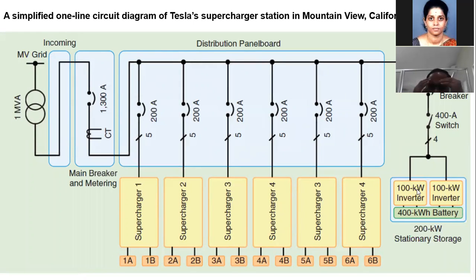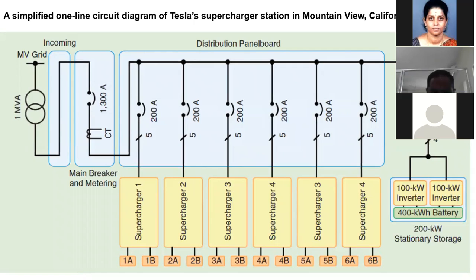To enhance the life of the grid level or large scale energy storage system, you can group the energy storage system into two. For example, if I have 500 kilowatt hour, I can split it into two groups of 250 kilowatt hour each. That's the key point to understand: if you divide the total capacity into two, while one group of batteries is involved in charging, the other group will be discharging to charge the EVs.